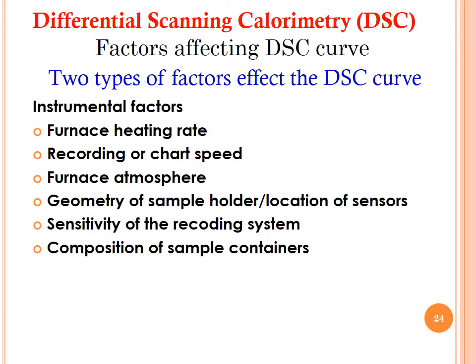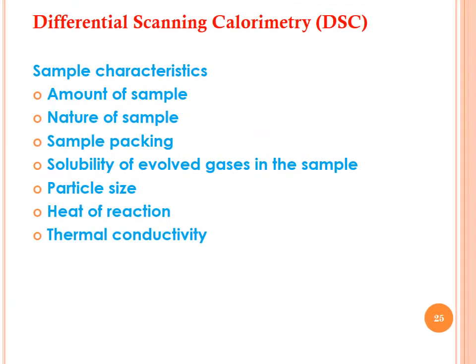Various factors affect the DSC curve. Instrumental factors include furnace heating rate, recording speed, furnace atmosphere, geometry of the sample holder, location of sensors, sensitivity of the recording system, and composition of sample containers. Sample characteristic factors include the amount of sample, nature of sample, sample packing, solubility of evolved gases in the sample, particle size, heat of reaction, and thermal conductivity.